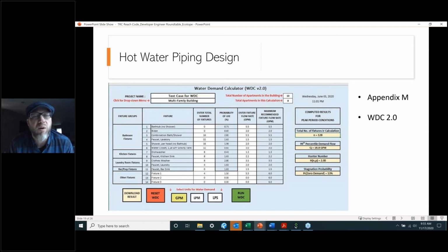Most of our hot water and cold water plumbing for our buildings designed around Hunter's curve are significantly oversized. We see flows that are probably 1/5 to 1/10 sometimes of what we're designing for. So you can get away with a lot smaller piping design if you're allowed to use these.